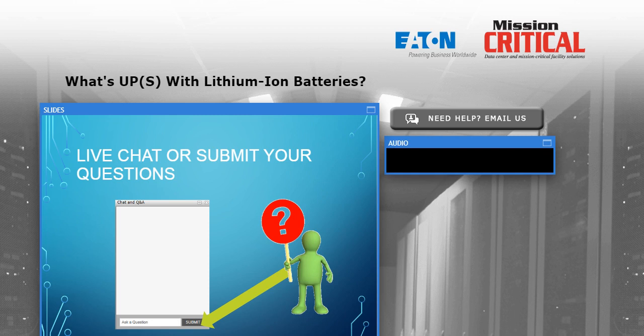And this is not an uncommon thing. So if you have a system or an arrangement on your site where I may have valve-regulated or flooded lead acid batteries and I want to put a string of lithium batteries in there as well, check the fire code, because the limits as to how much you can put in would be severely restricted. You can certainly deploy that battery in a separate room, but if I'm going to put them in the same room, different chemistries in the same room, the limits are significantly lowered.